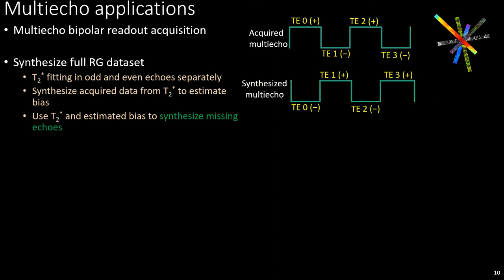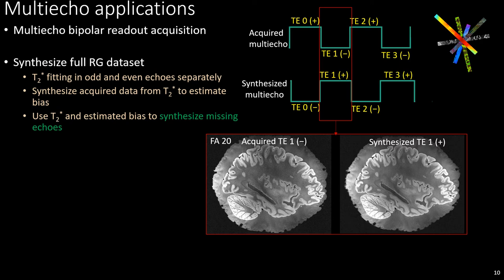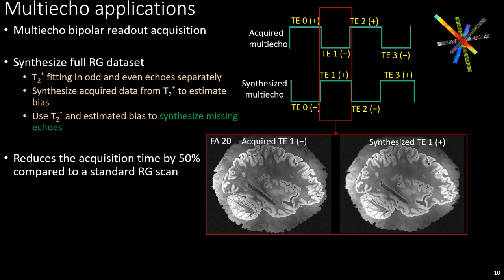Moving to multi-echo applications, the multi-echo sequence encodes bipolar readouts. A reverse gradient scan would involve repeating this bipolar scan with opposite readout polarity. Instead, we choose to synthesize the reverse polarity scan from a single bipolar acquisition. The synthesis involves first fitting T2-star in the odd and even echoes separately, then estimating a multiplicative bias in the T2-star estimates at every voxel, and using both to synthesize the reverse polarity echoes. This gives us both readout polarities for every echo, and saves 50% of scan time by removing the need to acquire the reverse polarity data altogether.